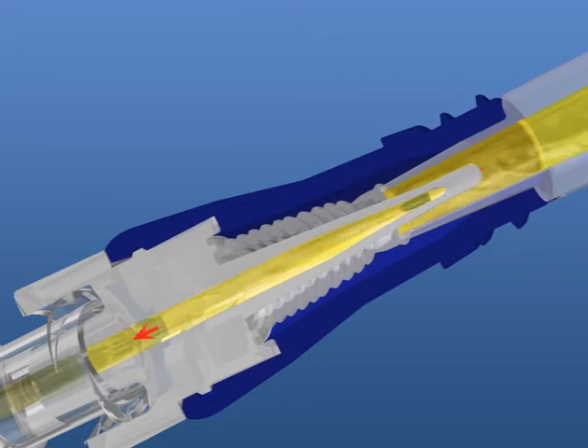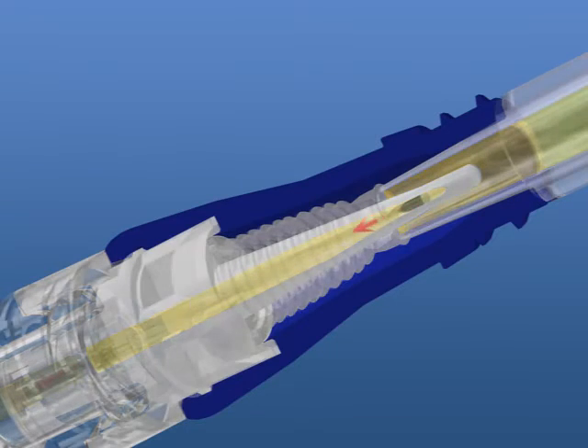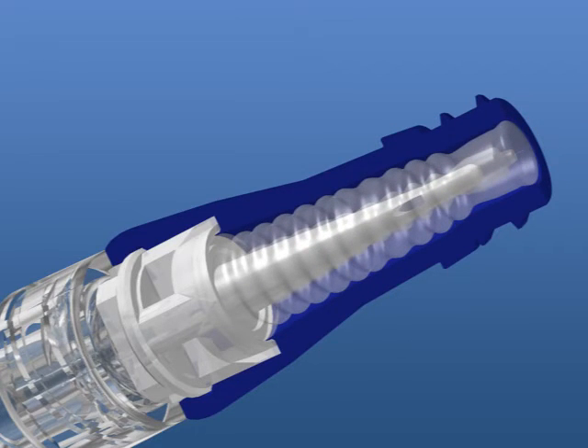The Microclave maintains a flow rate at gravity of 165 milliliters per minute, which is greater than an 18-gauge needle. When the access luer is removed, the septum returns to cover the cannula and closes the fluid path once again.